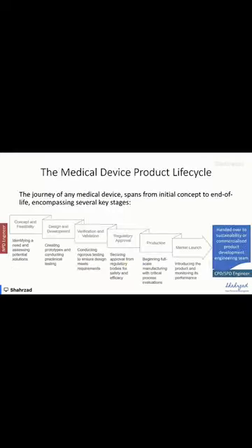Moving on to the medical device product life cycle. The journey of any medical device spans from initial concept to end of life, encompassing several key stages, as you can see on the screen. So anything from concept and feasibility to production and market launch, all of those stages require a new product development engineer to work on them, develop documentation, make sure everything is in accordance with the regulatory requirements.